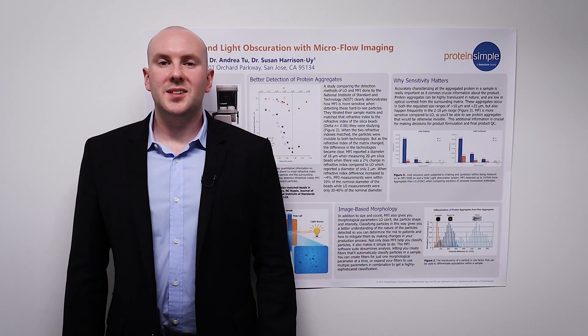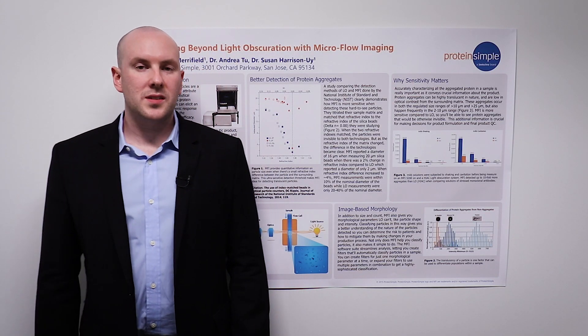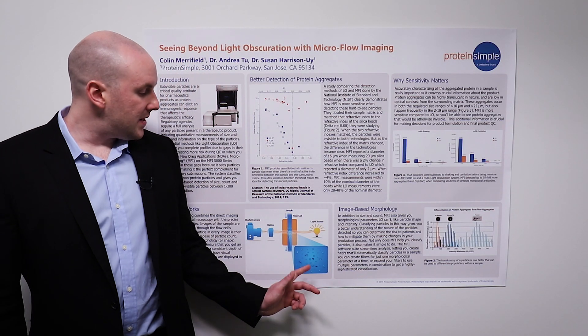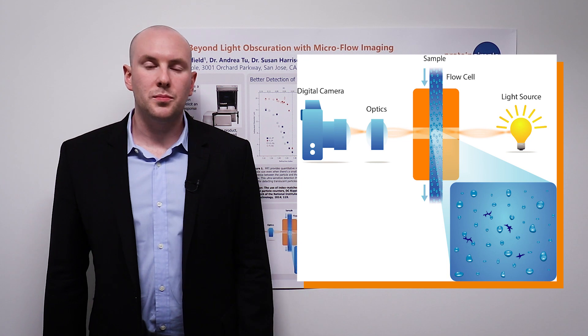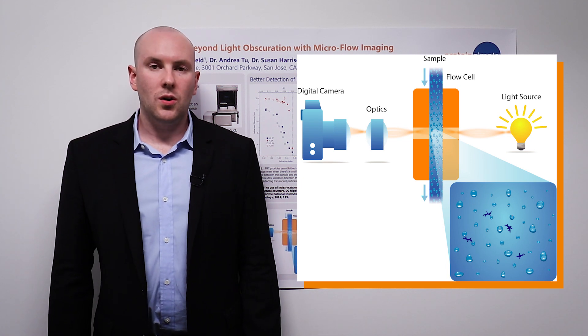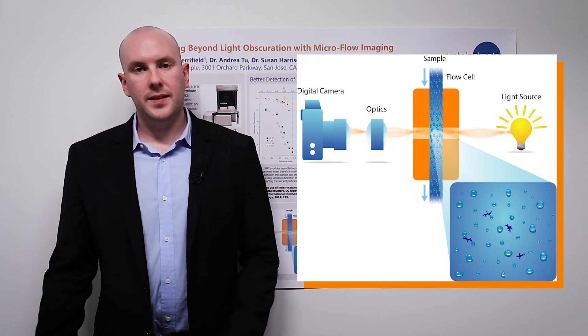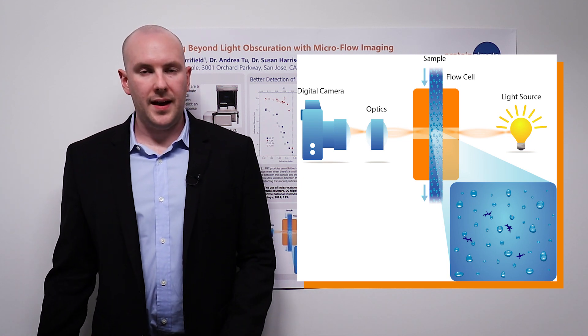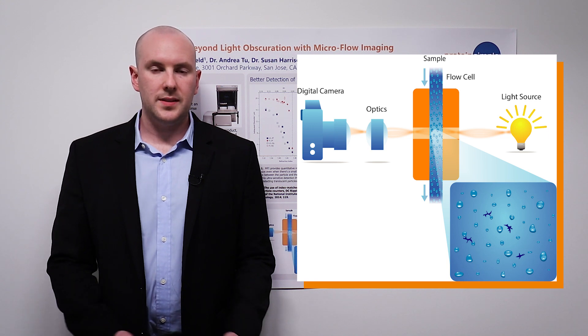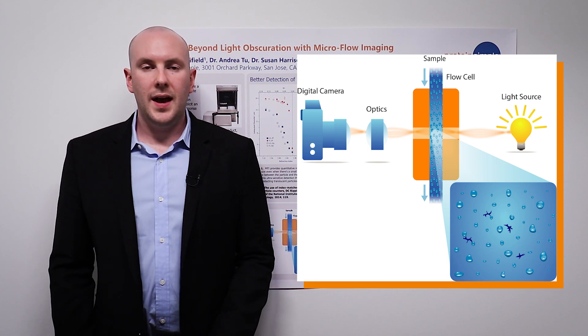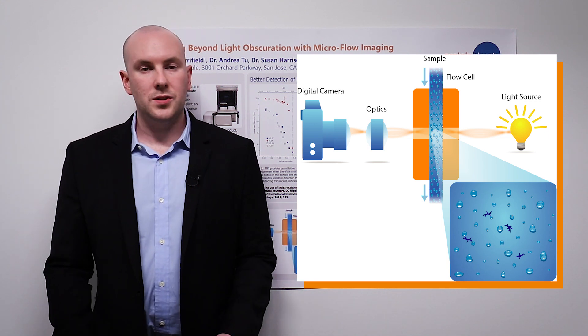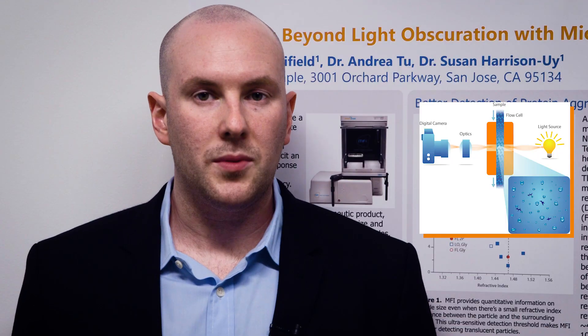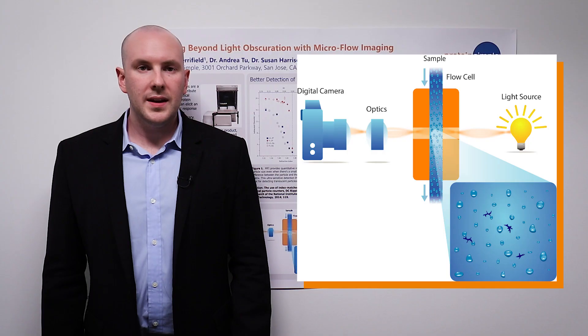To begin, I'd like to talk a little bit about how MFI works. MFI is based on the concept of brightfield microscopy. On one side of the sample, we have a light source which illuminates the sample, and then on the other side we have our optics, which focus a camera that then images the sample as it passes by.